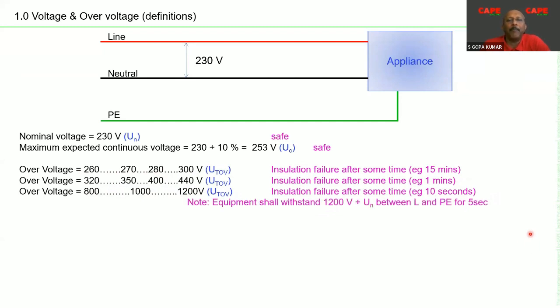This is an example. Now, we must also understand that these are line to neutral, but between line to earth, due to a high voltage fault, all equipment which we connect to a line must be able to withstand 1200 volt plus nominal voltage, meaning about 1450 volt between line and PE for 5 seconds. This is a standard requirement. Now, what I wanted to tell you is, under normal condition, your equipment is safe. Under maximum continuous operating voltage, your equipment is safe. Under temporary overvoltages, your equipment may withstand a certain time depending upon the voltage.